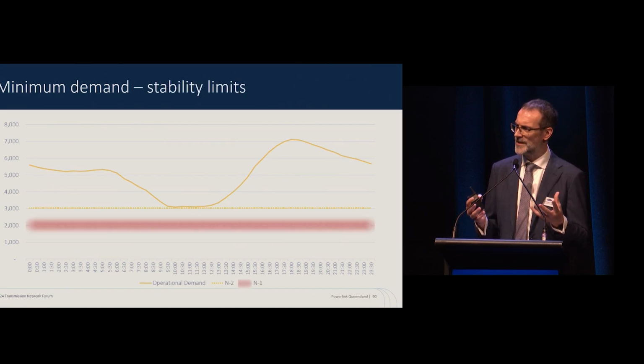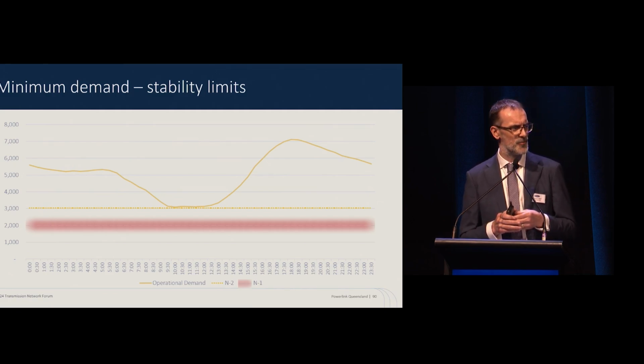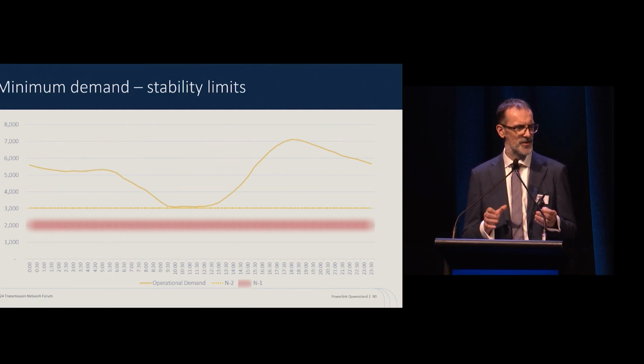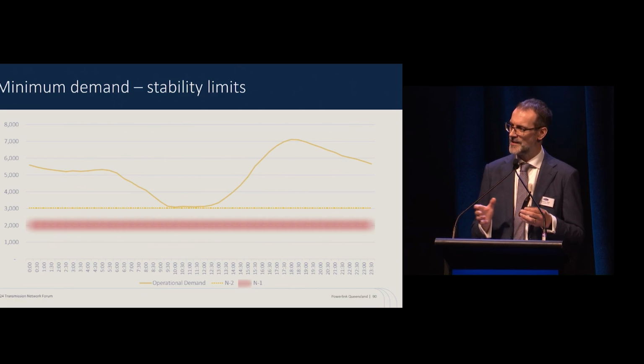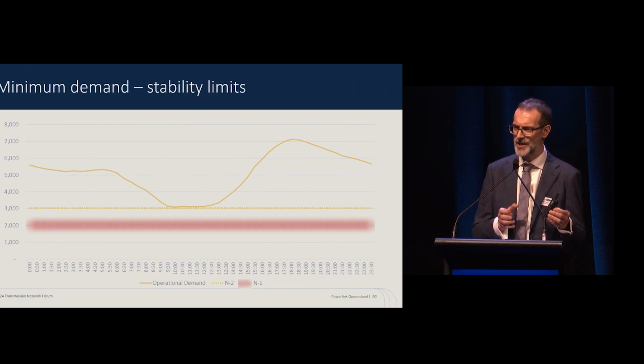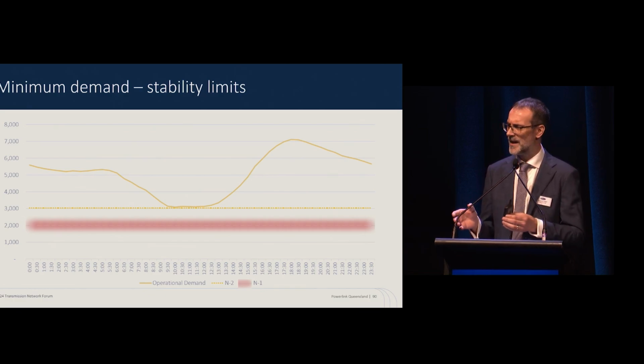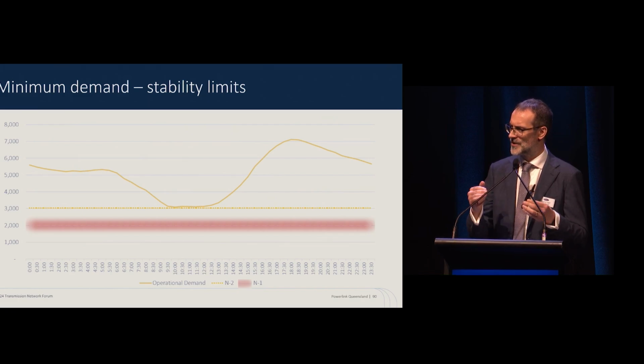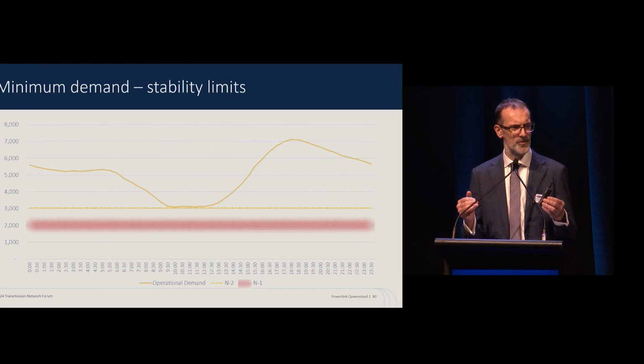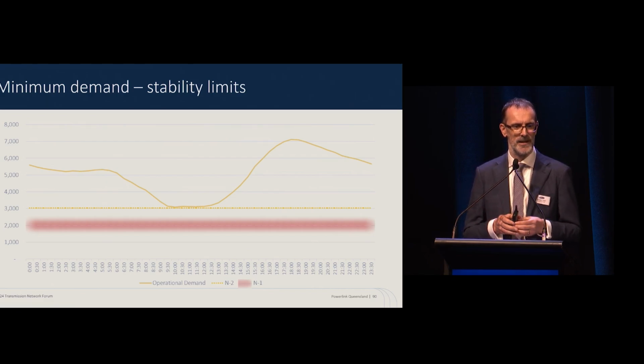So where are the stability limits? The first one, the dotted line, that's the N-2. That's when we start to get nervous. If two things go wrong, either from a generation, transmission, or load perspective, all of a sudden the system becomes unstable. That's at 3,000 megawatts, which is basically where we were in October this year.